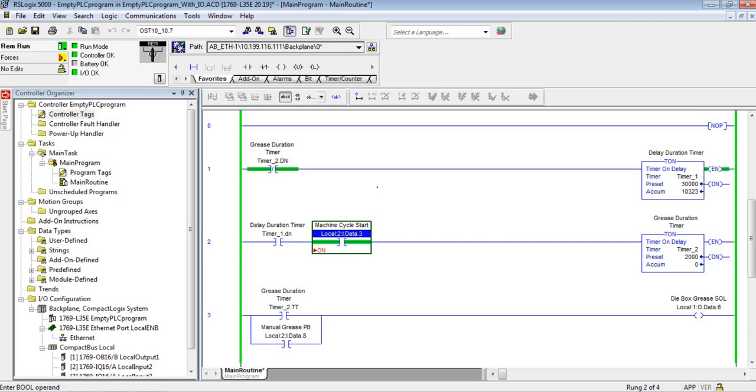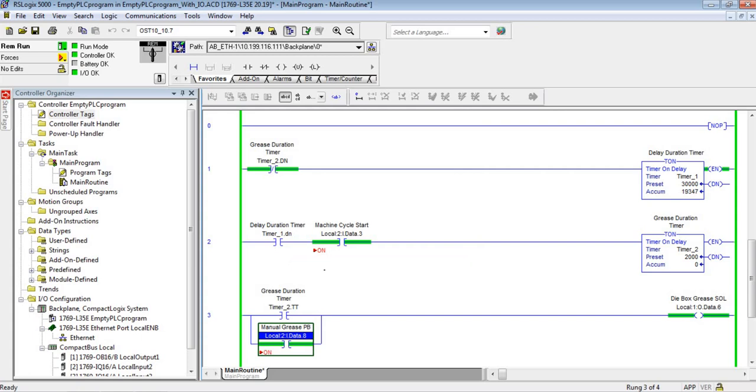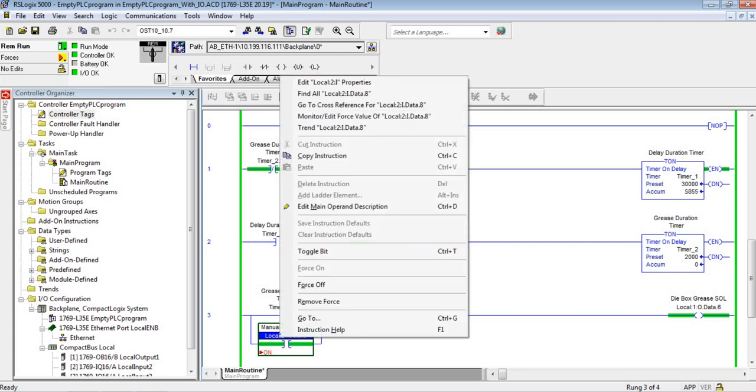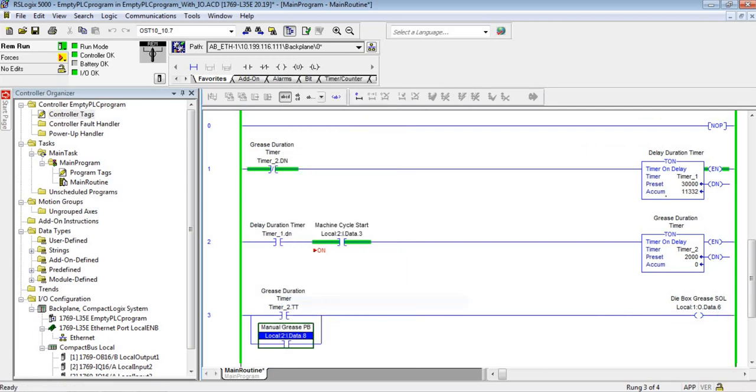There's also a manual push button right here. Let's right-click on that and force it on - that's going to simulate someone holding the manual push button on the operator panel. Now, do you see a problem with this? My duration timer did not reset. I'd like it to not run when I'm holding the manual grease button, because if I hold manual grease and then let go, but my timer is already way up there, it's going to grease again very shortly.